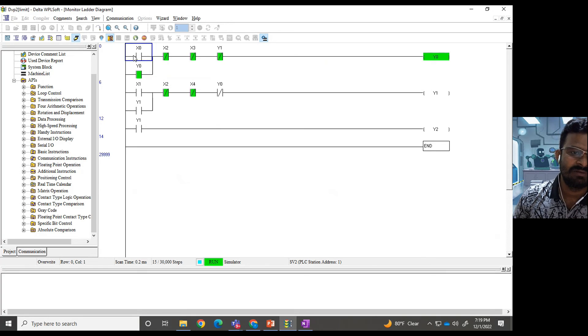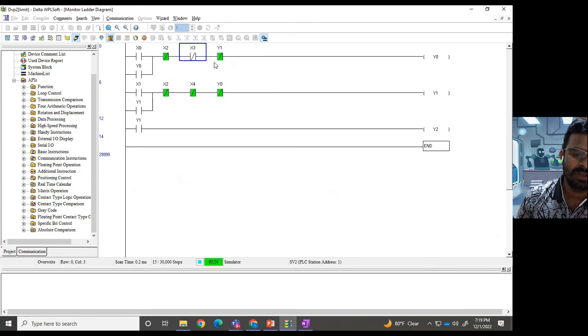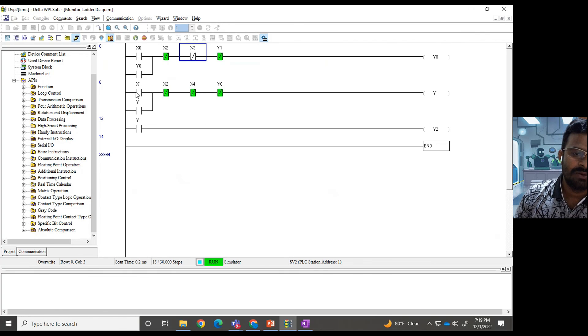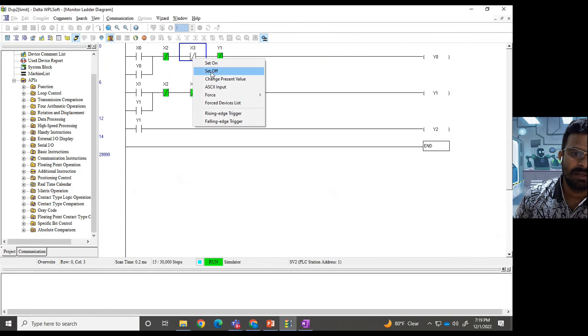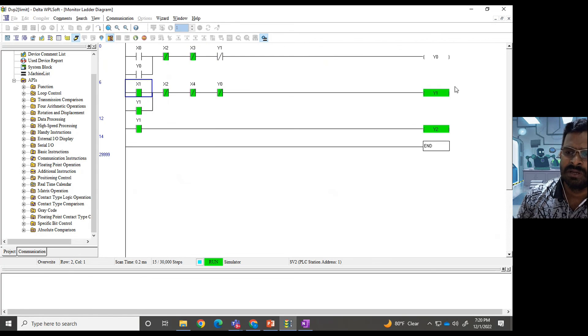Even if I release the push button, power flow continues through the latched path and the pump stays on. When it reaches the upper position, X3 — that is limit switch LS1 — gets activated, so the power flow stops to the coil, the coil gets de-energized, and the pump turns off. Now the operator operates the down switch, so control relay Y1 is energized and the solenoid gets energized.